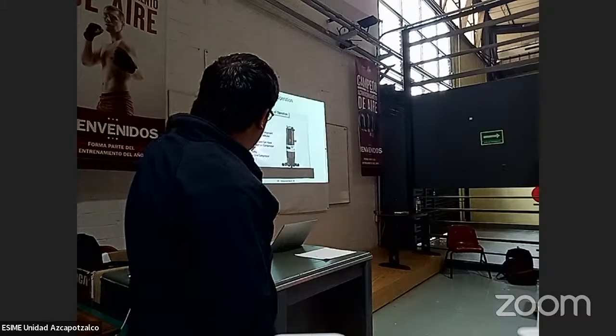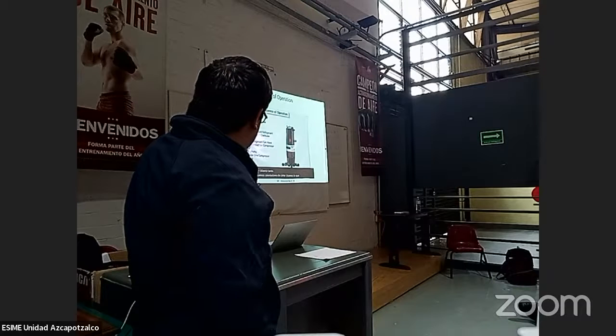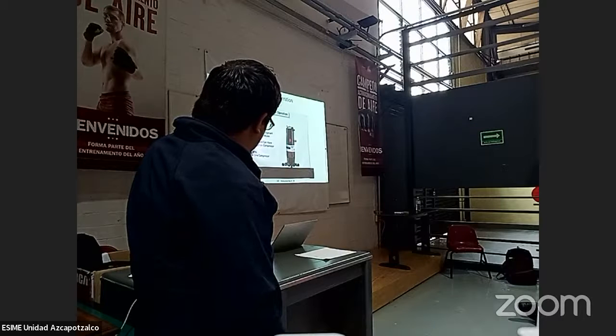Compressor stator heat. On these units, we don't use crankcase heaters. We use what we call stator heat. It prevents liquid refrigerant from settling in the crankcase. Liquid refrigerant can have an adverse impact on compressors, as you know. How it works is we energize one compressor winding, which will generate watts of heat, which keeps that compressor warm. We make sure that when it sees a certain temperature outside, it will initiate that and bring it on. If it's 95 degrees outside, we don't need to operate that one.